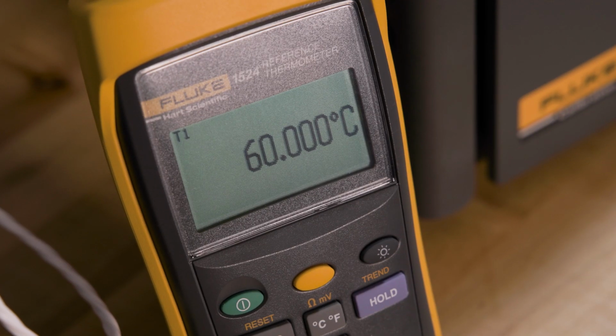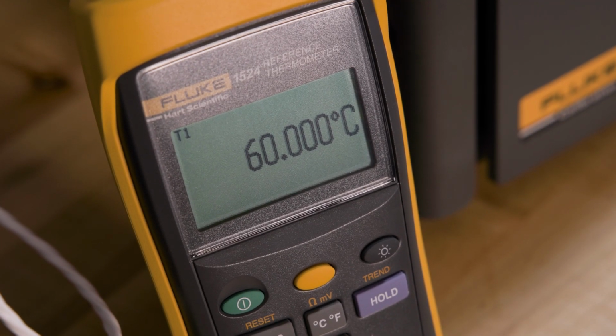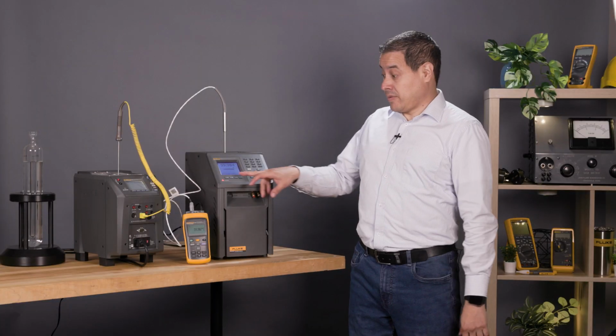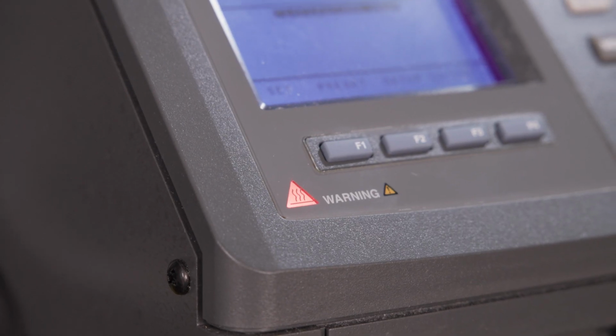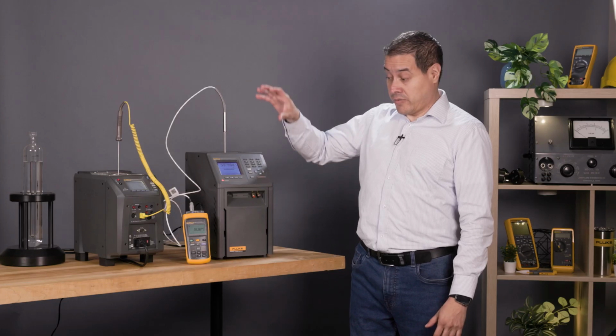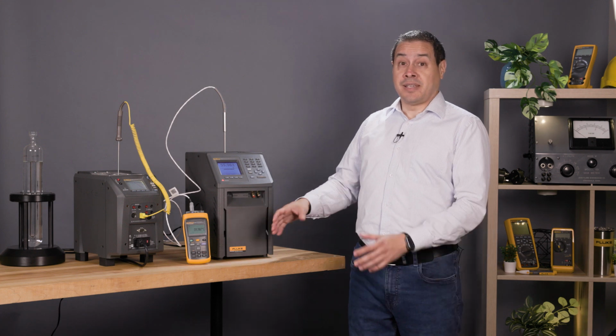Next set points, do the same procedure, and when you finish, be careful, don't remove the probe if the warning sign is on, because you may get burned. Once you follow all the calibration procedure points and you have all your measurements, pay attention, the warning light is off, so you can safely remove your probe, you can remove your unit under test, and the calibration is done. And this is how you calibrate a handheld thermometer with a dry well, in this case a 9173.